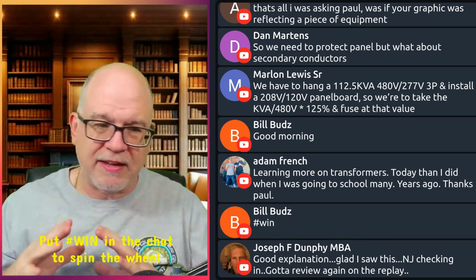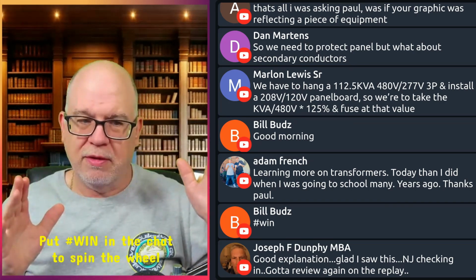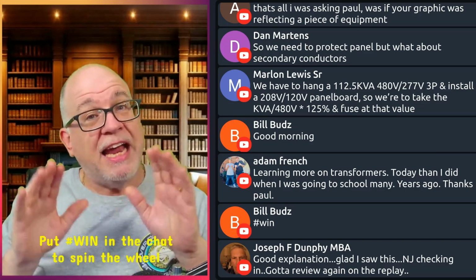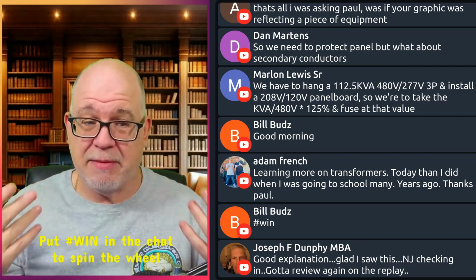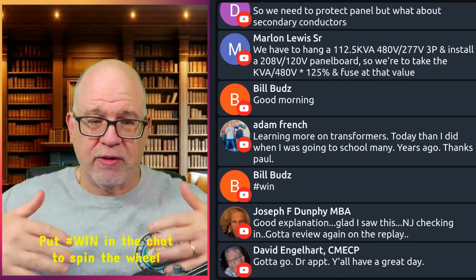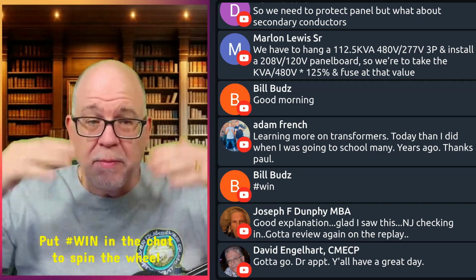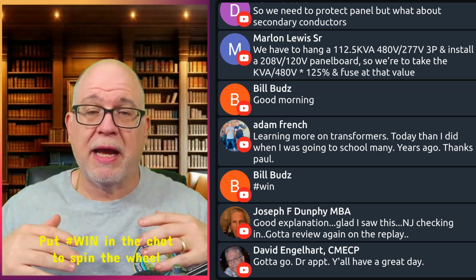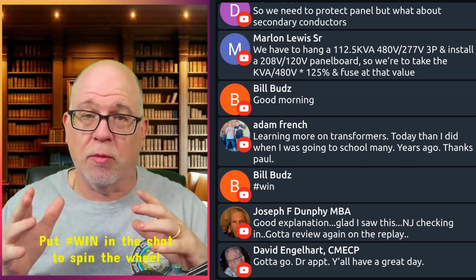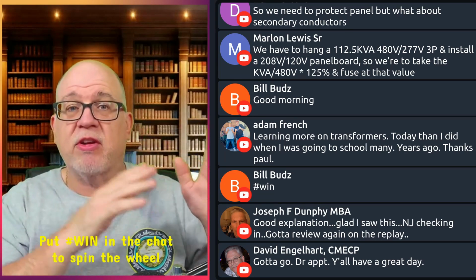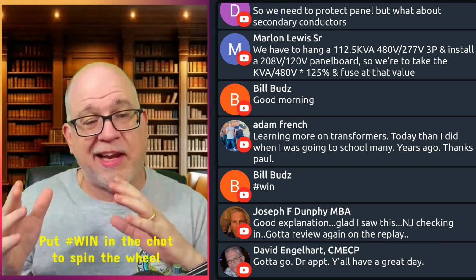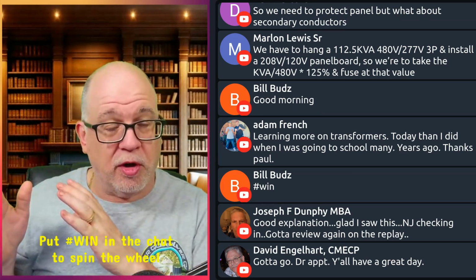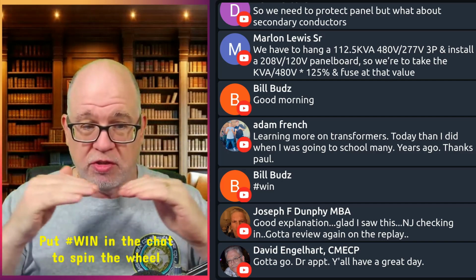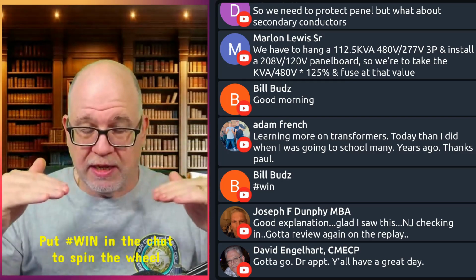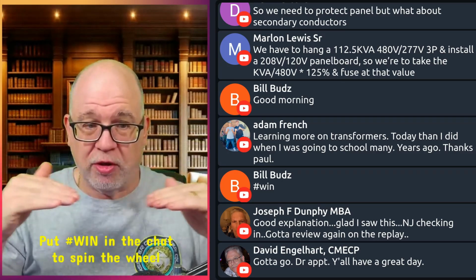We haven't sized any conductors or anything. We're just talking protection right now. Okay, so that is a rarity, and I went extremely deep into that. So if there's confusion there, remember, we were only talking about primary protection of the transformer, and when the primary protection of the transformer can also protect the secondary and the panel board under those unique conditions. Okay, unique conditions. That's what we were talking about.